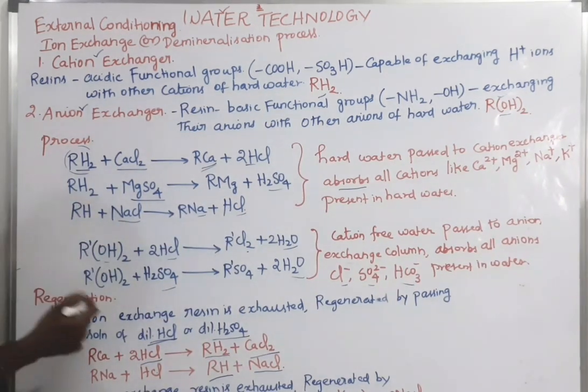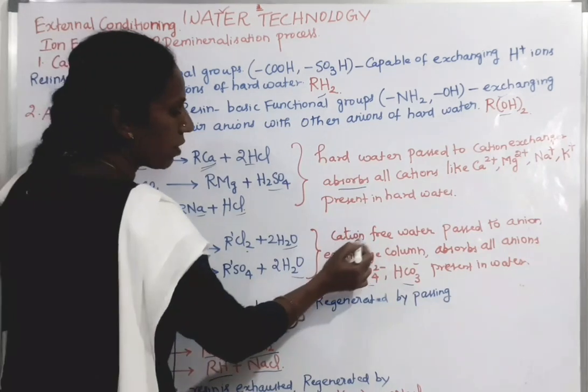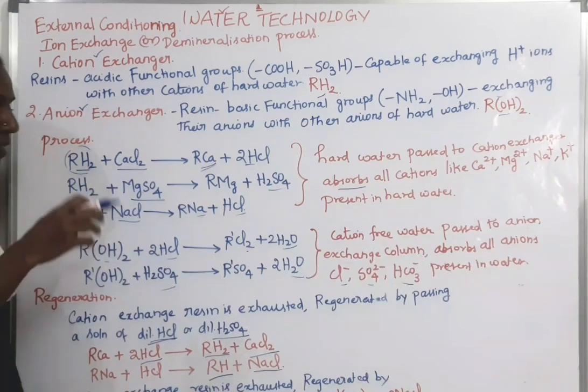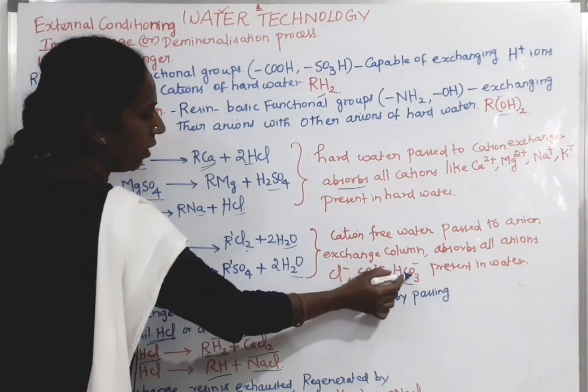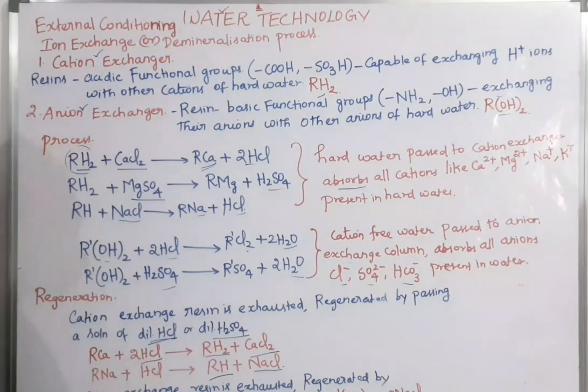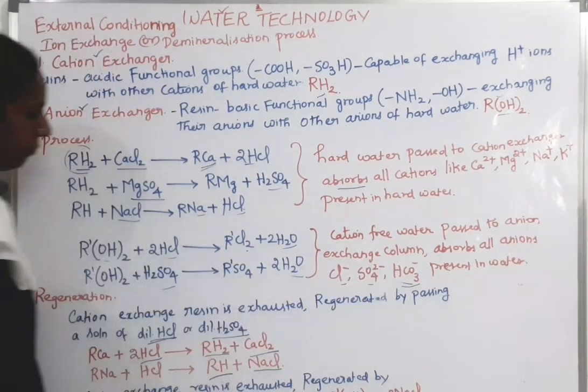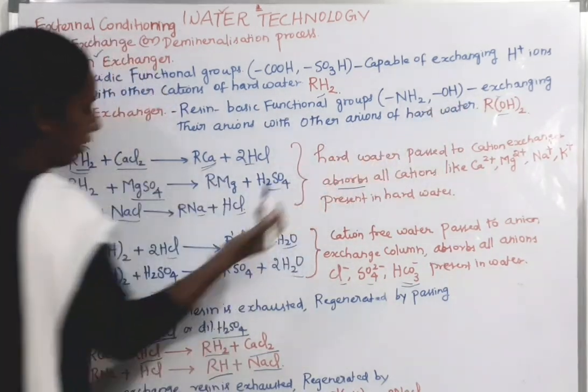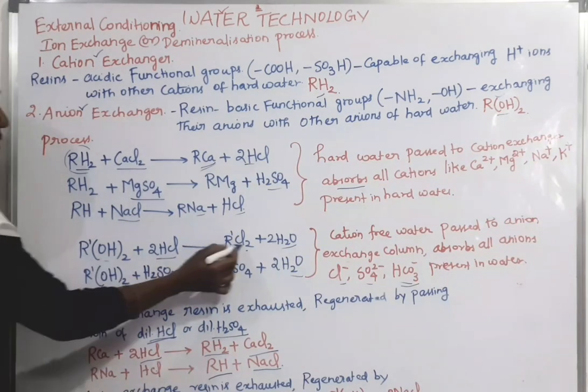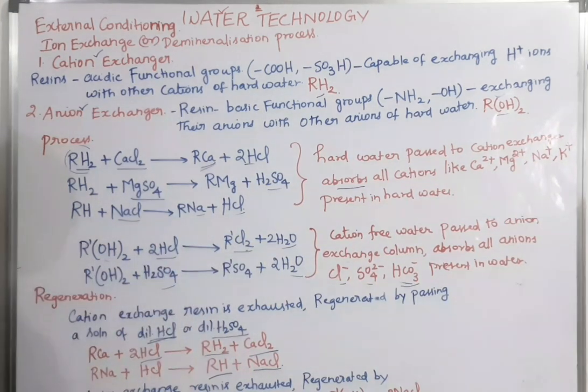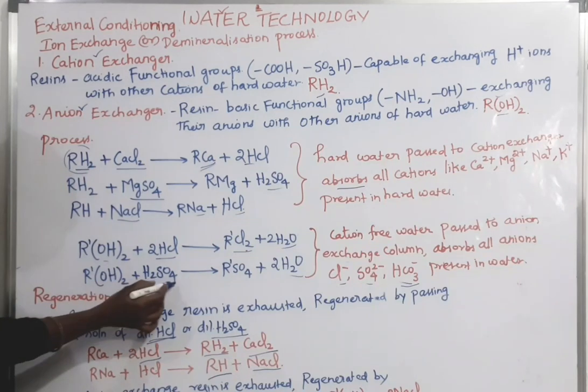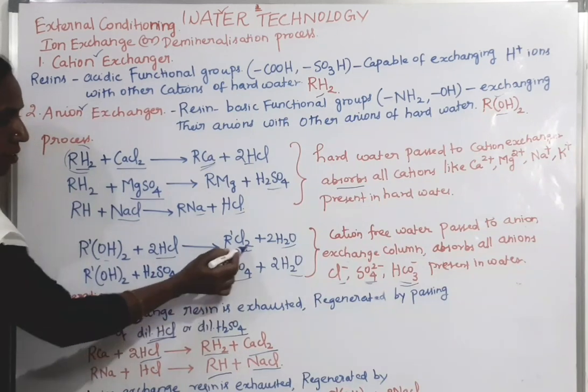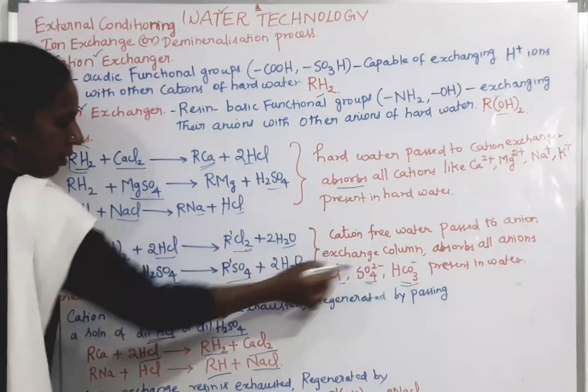In the next step, the water which is free from cations is passed into the anion exchange column, which absorbs all the anions present in the water — that is, Cl⁻, sulphate, and HCO3⁻ (bicarbonate). The reactions are: R(OH)2 plus 2HCl gives R·Cl2 plus water, and R(OH)2 plus sulphuric acid gives R·SO4 plus water, absorbing the Cl⁻ and sulphate ions.